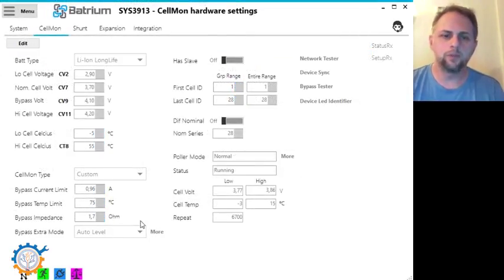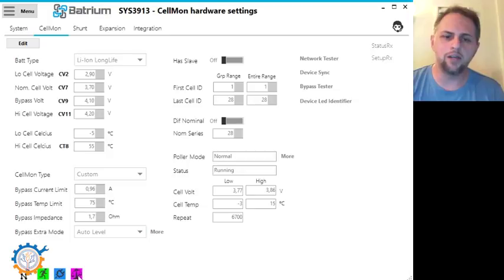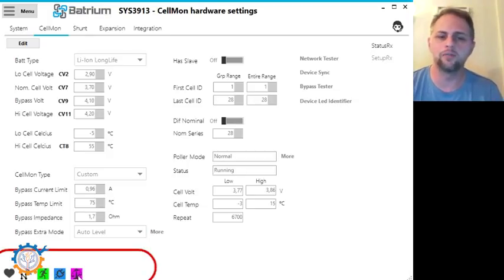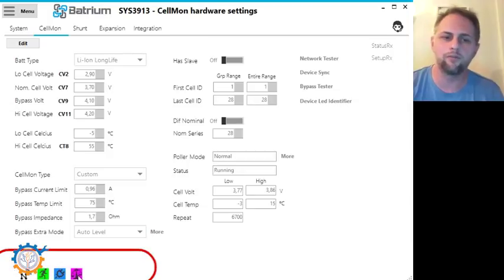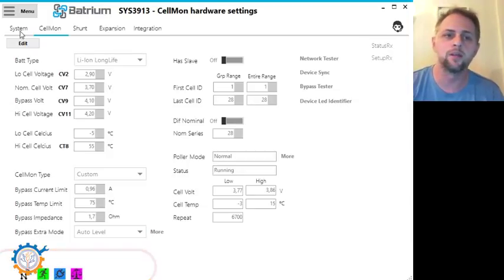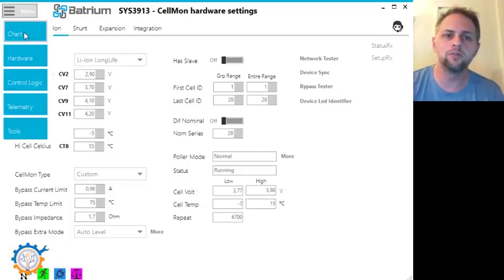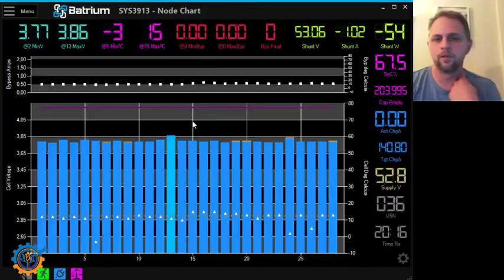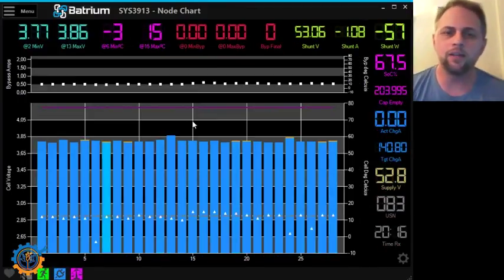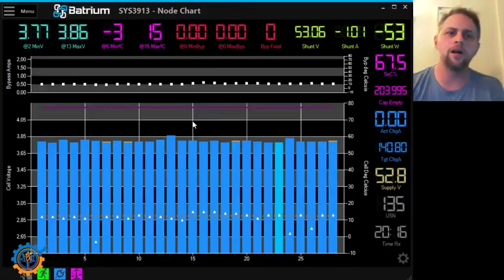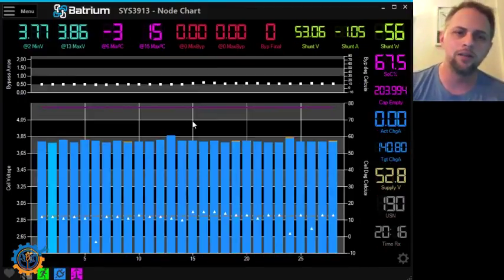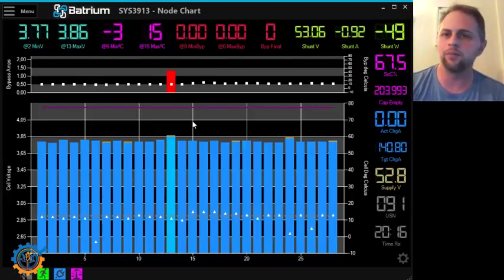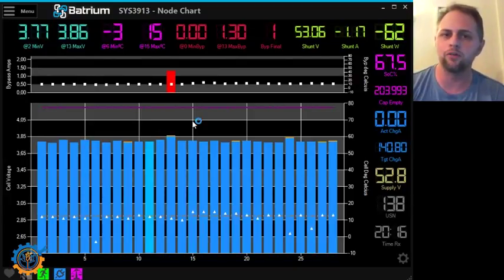So what you see now is that this icon came up. This icon means idle bypass adjustment is running. That's the auto level function that we just enabled. So let's go back to the dashboard. So basically what will happen now is that the cells that are in a banding of 0.05 volt should start to balance.